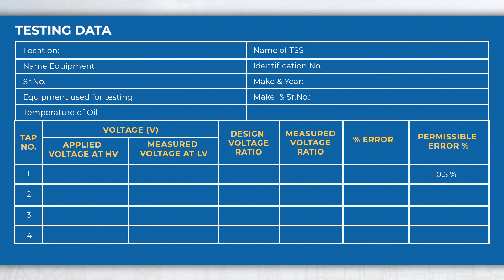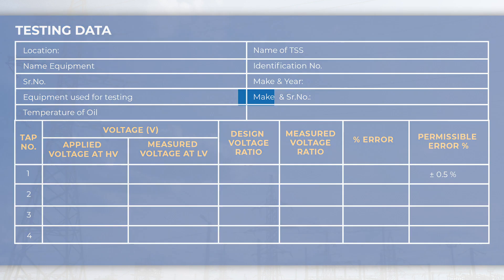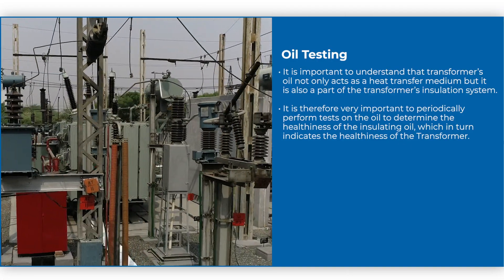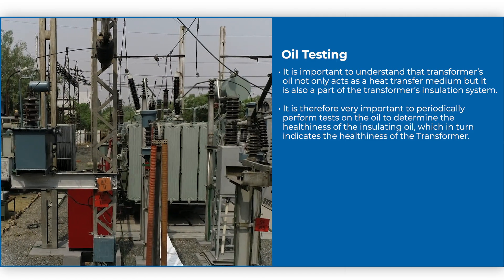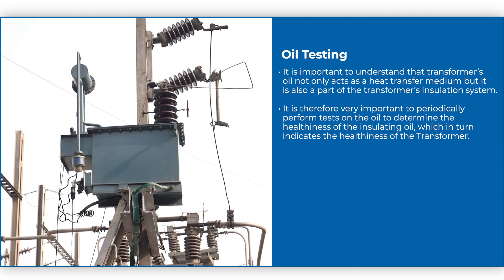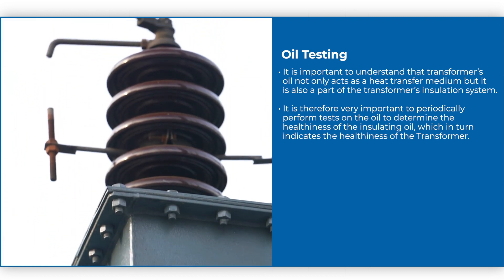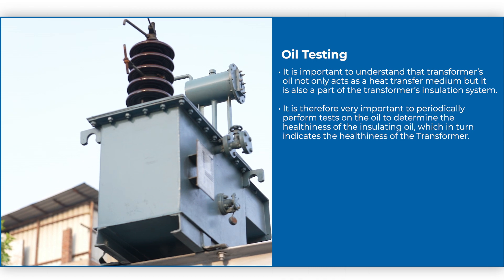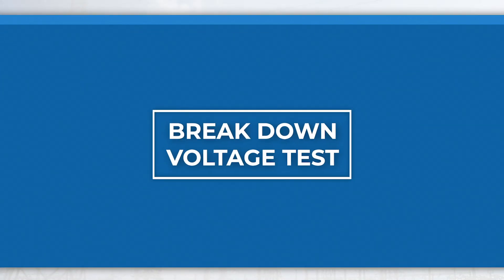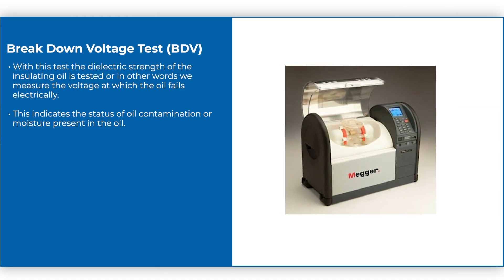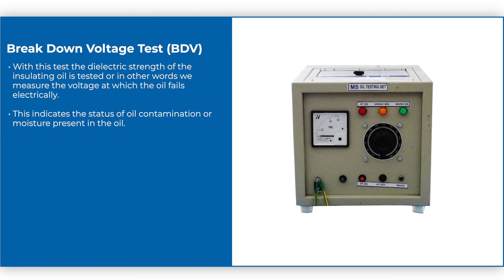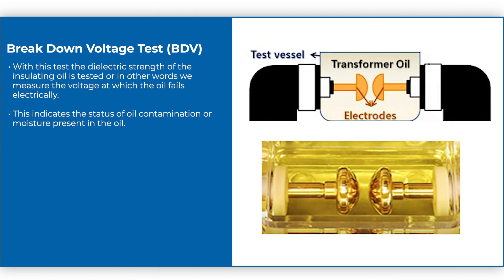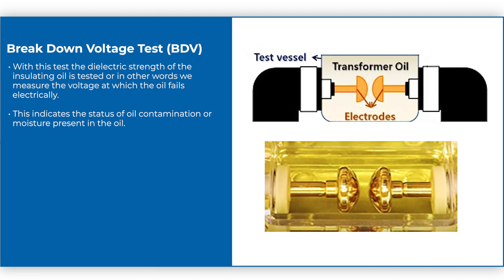Oil testing: It is important to understand that transformer oil not only acts as a heat transfer medium but is also a part of the transformer's insulation system. It is therefore very important to periodically perform tests on the oil to determine the healthiness of the insulating oil, which in turn indicates the healthiness of the transformer. Break down voltage (BDV) test: With this test, the dielectric strength of the insulating oil is tested; in other words, we measure the voltage at which the oil fails electrically. This indicates the status of oil contamination or moisture present in the oil.